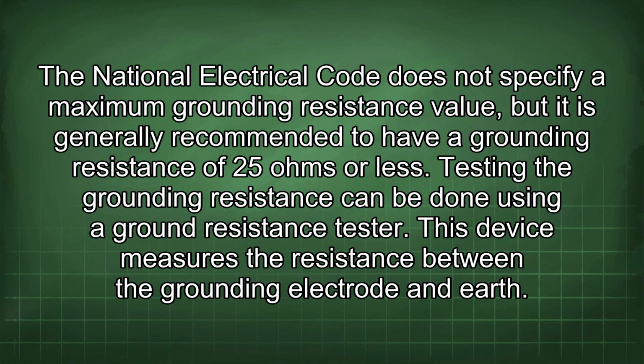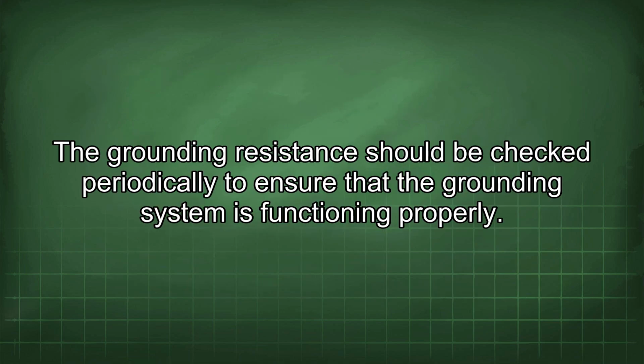Testing the grounding resistance can be done using a ground resistance tester. This device measures the resistance between the grounding electrode and the earth. The grounding resistance should be checked periodically to ensure that the grounding system is functioning properly.